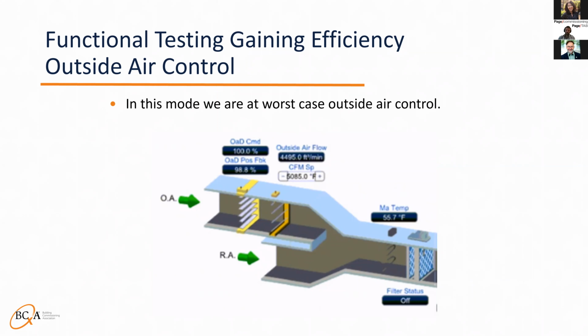Sometimes the terminal unit's heating CFM will add up to less than the total outside air of the AHU. Ideally, this is caught in the design phase, but it's never too late to catch an issue. Outside air should always be controlled to its ASHRAE 62.1 minimum set point, unless you have CO2 sensors in the space or a combination of CO2 sensors and occupancy sensors.